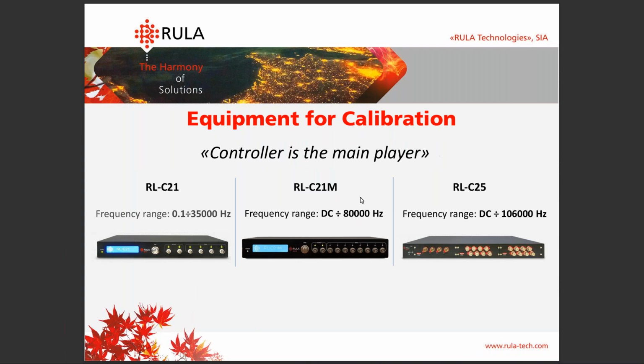So another thing that we wanted to feature is the controller. We're starting here to explain what equipment you're going to need for calibration of the listed type of devices. And we at RULA think that the controller is the main player, the key, because it is the controller that is going to perform all the calculations. And we manufacture and provide a range of vibration controllers that are going to cover all the needs for a calibration lab. And you can see our range here. For now, it's RLC21, RLC21M with 8 channels, and RLC25, the modular system. You can see that the main difference is in the frequency range that you're going to be focusing on in case of calibration.